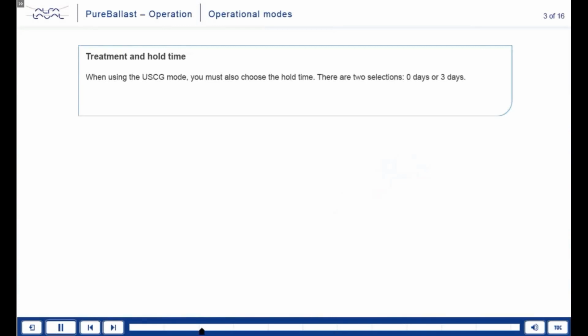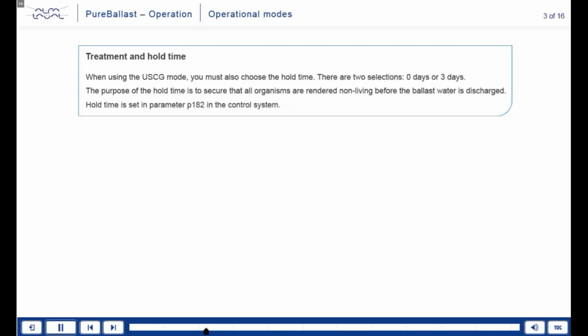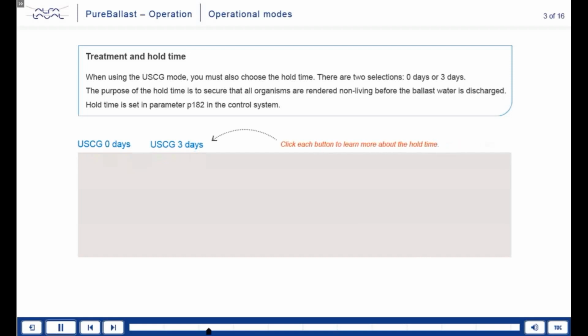When using US Coast Guard mode, you must also choose 0 days or 3 days. The purpose of holding the ballast water in the tank is to secure that all organisms are rendered non-living before the ballast water is discharged. Hold time is set in parameter P182 in the control system. Here's how the hold time looks in the US Coast Guard mode. Click each button to learn more about the hold time.